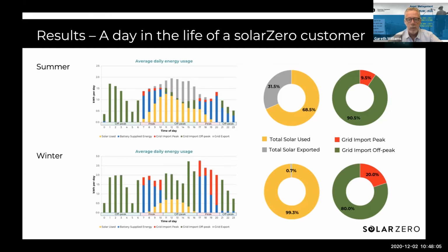So you start seeing the battery filling up in the late afternoon, and export starts increasing. Every day we top up the battery from the grid, typically between 3 and 5 o'clock, to make sure the battery is 100% full ahead of the evening peak.